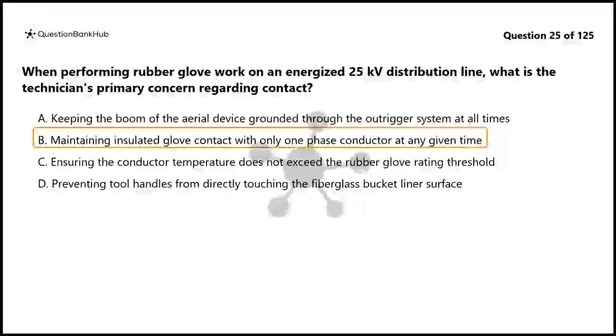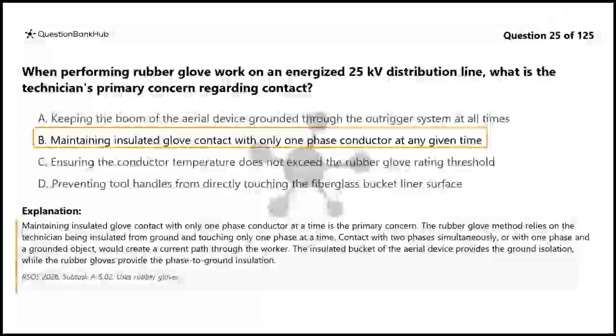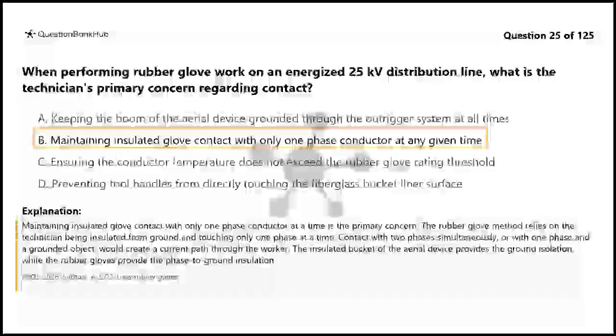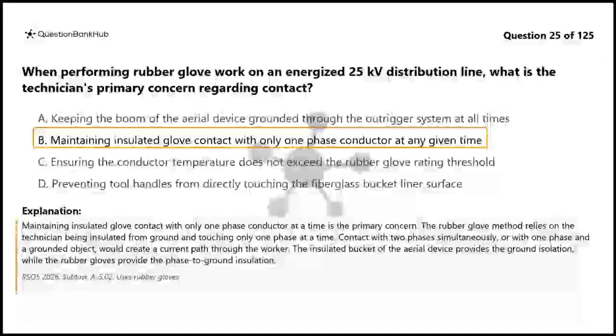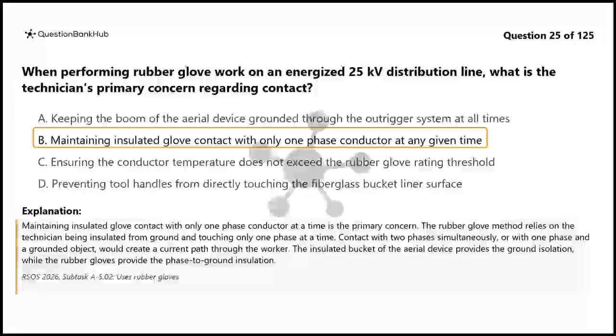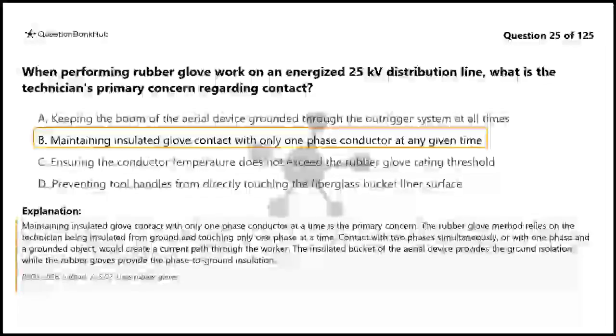The correct answer is B. Maintaining insulated glove contact with only one phase conductor at a time is the primary concern. The rubber glove method relies on the technician being insulated from ground and touching only one phase at a time. Contact with two phases simultaneously, or with one phase and a grounded object, would create a current path through the worker. The insulated bucket of the aerial device provides the ground isolation, while the rubber gloves provide the phase-to-ground insulation.